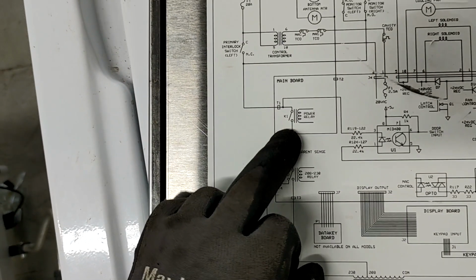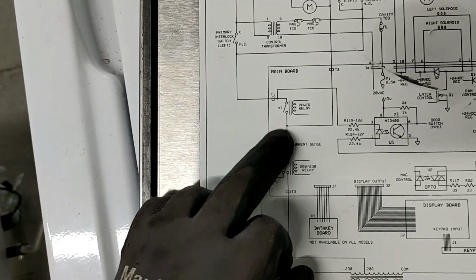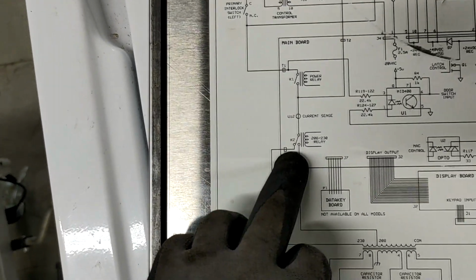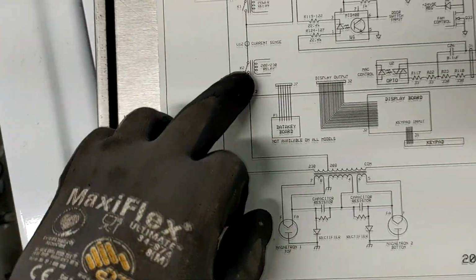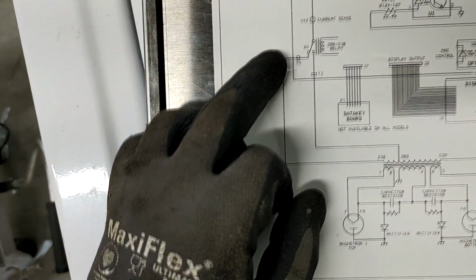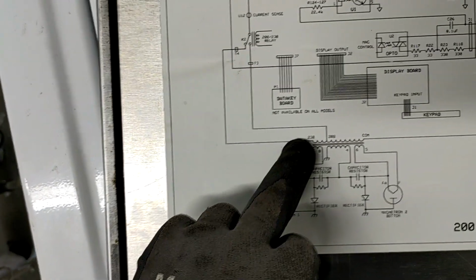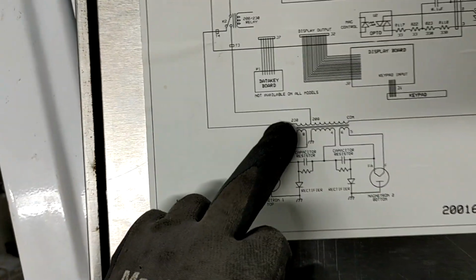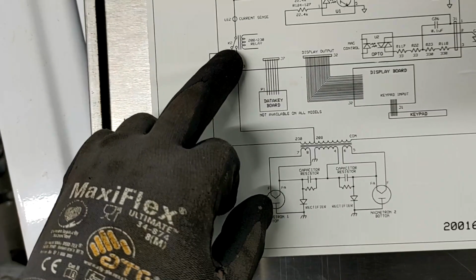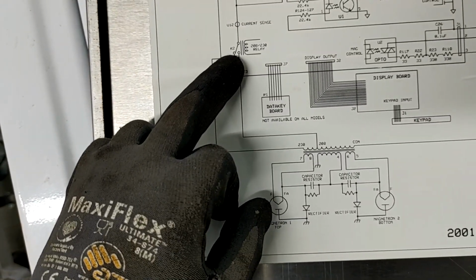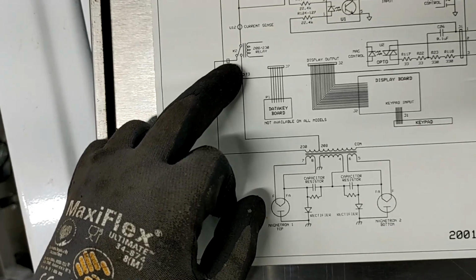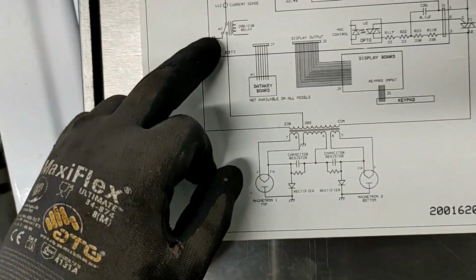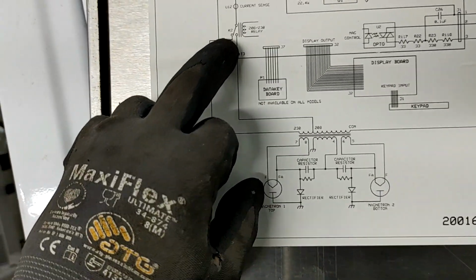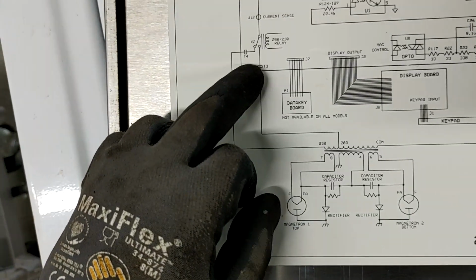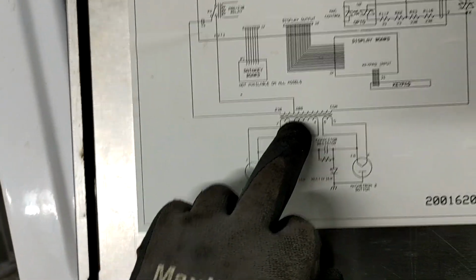From T1, relay K1 sends power down to K2, and depending on the type of power source: if you got 230 volts, it's going to go out on T4 and come out to that side of the actual transformer. If you got 208 voltage in your restaurant, it's going to come down and go out on T3 right there.